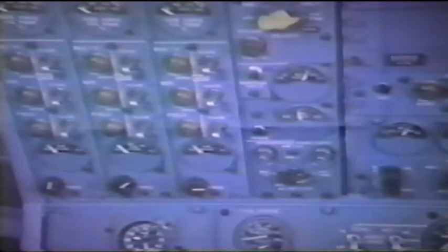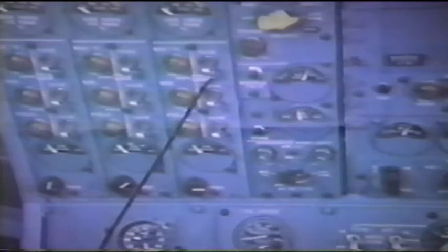Once again, if we could never get a slow enough frequency so that we felt confident and comfortable that we could manually parallel, one thing we could do would be to open the generator breaker, close the bus tie breaker, because we would not have to manually parallel if there were no conflicting power source vying for the attention of bus number 3. And then we could quickly close the generator breaker and let the automatic paralleling sequence take over. And that's what's called chicken paralleling, if you want to call it that.